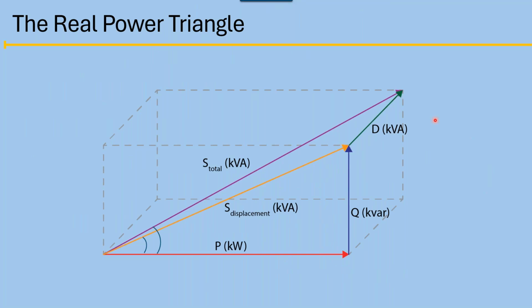What's interesting here is, and I'll show this in more detail in another slide, if I look at the power factor, which is kW over kVA, this one's going further away. I'm always going to see the total kVA power factor lower than the displacement kVA power factor. And there's actually a paper that says if I know both these kVAs and I know the power factors of these two, then you can actually calculate what your harmonics are, which is kind of interesting.